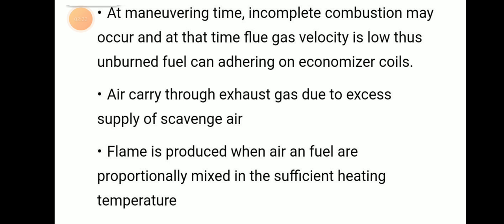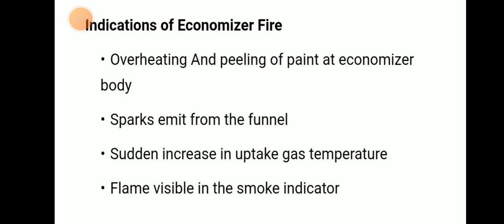The indications of economizer fire are: overheating and peeling of paint at the economizer body; sparks emitting from the funnel; a sudden increase in uptake gas temperature; and a flame alarm with flame visible in the smoke indicator.